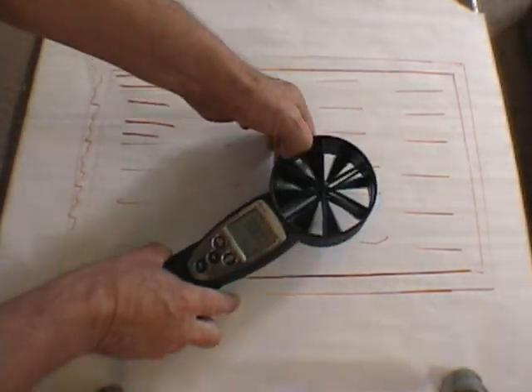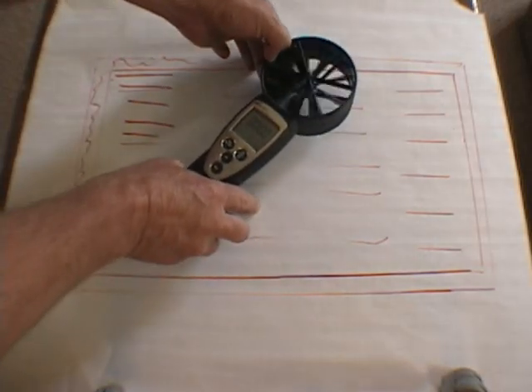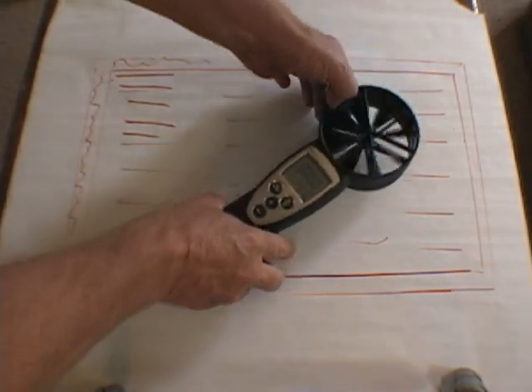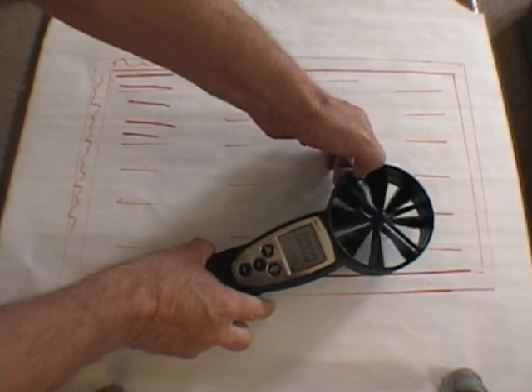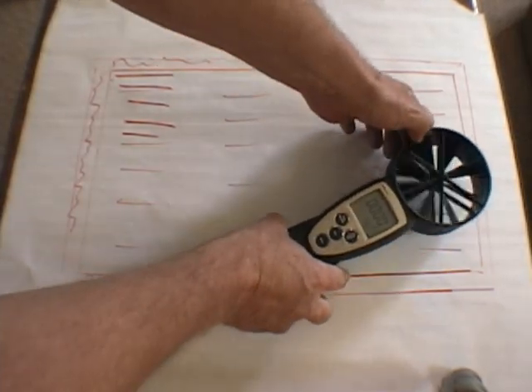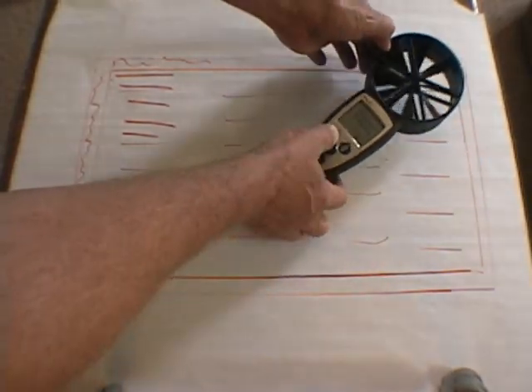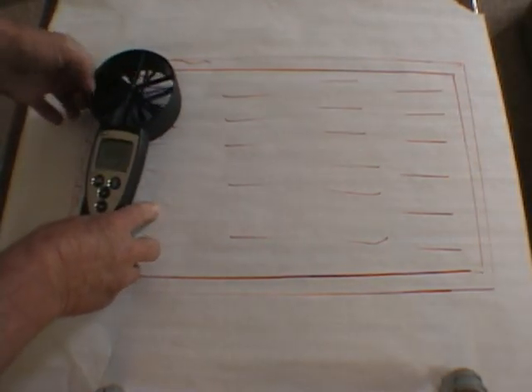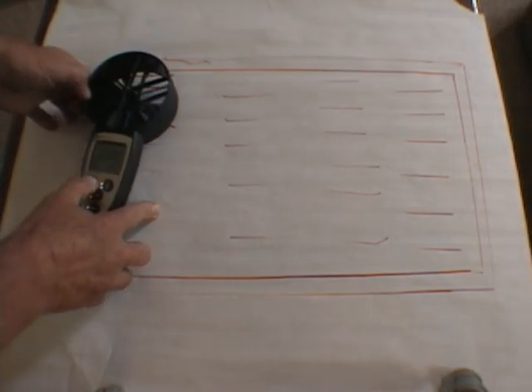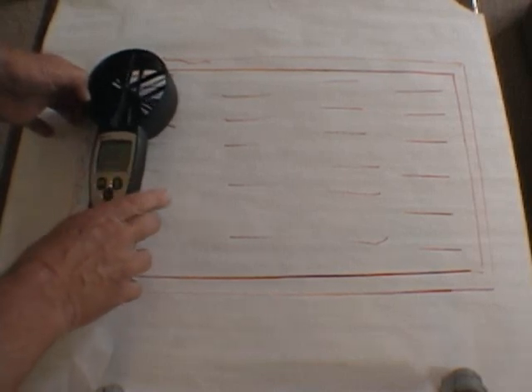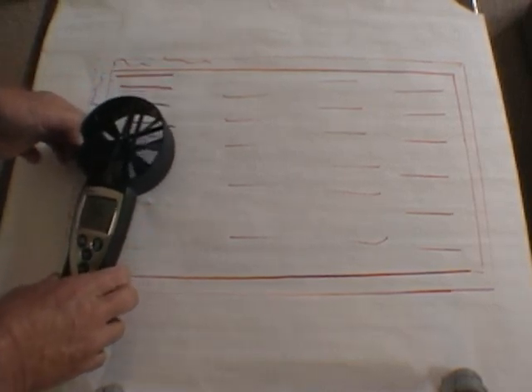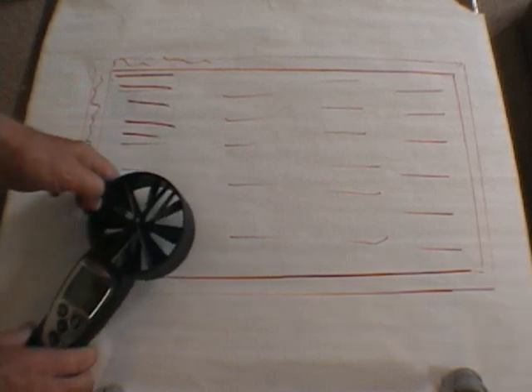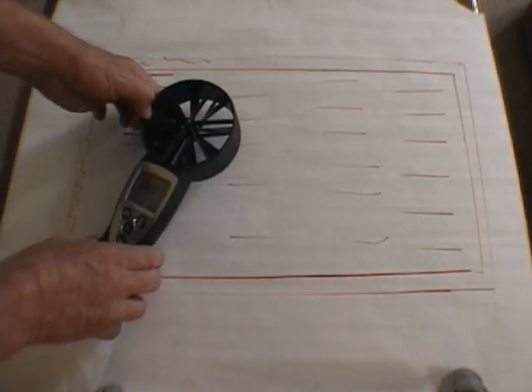I want to move at four seconds per foot, linear foot or slower to give time for the little vane there to speed up and slow down and take our measurement. When I do this, I'm going to hold it in the corner, let this vane get up to full speed, and press the timer.